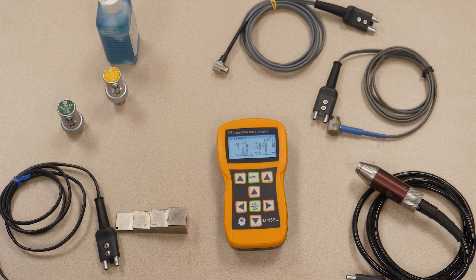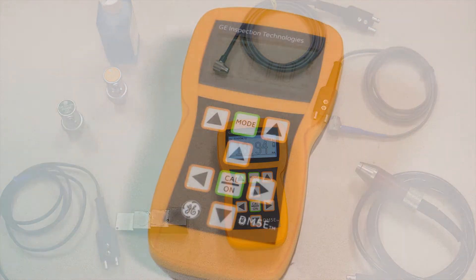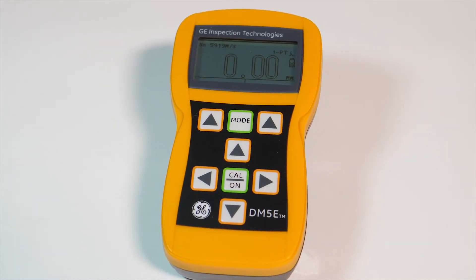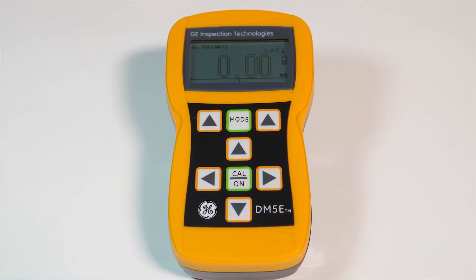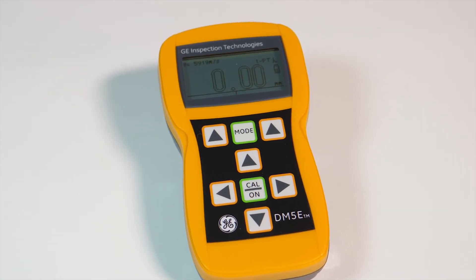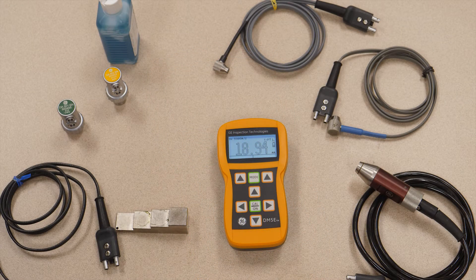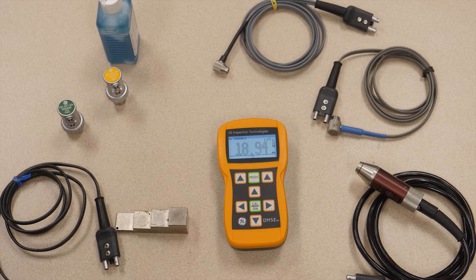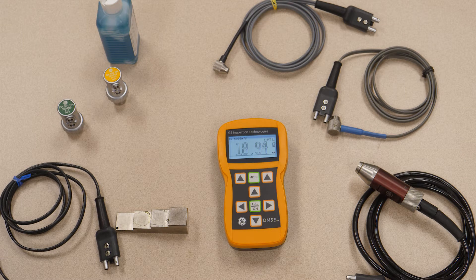Today I'd like to show you a little bit about the DM5E. It's our basic corrosion thickness gauge, typically used for inspecting steel pipe or looking for corrosion in piping, tanks, and other vessels. It has a precision of three decimal places of an inch, two decimal places of a millimeter, so a hundredth of a millimeter or one thousandth of an inch.